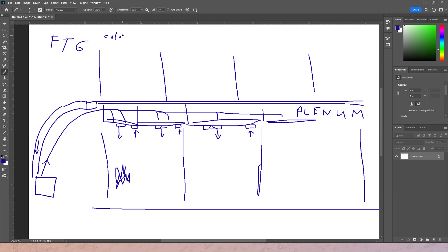If the fire gets into the ceiling as well, the wires can catch on fire and produce toxic fumes that can possibly enter other rooms. So in this case, a different type of cabling has to be implemented. If it's a cold air return plenum, the cable has to be rated FT6. That's the FT6 cable. So for a cold air return plenum, FT6 wire has to be implemented.